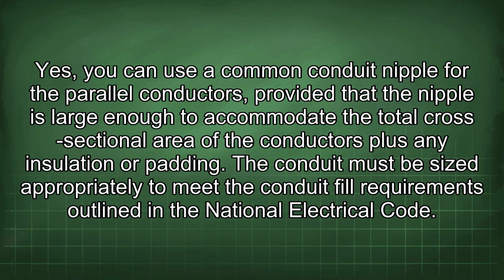Yes, you can use a common conduit nipple for the parallel conductors, provided that the nipple is large enough to accommodate the total cross-sectional area of the conductors plus any insulation or padding. The conduit must be sized appropriately to meet the conduit fill requirements outlined in the National Electrical Code.